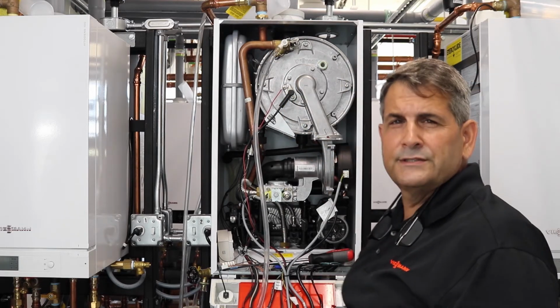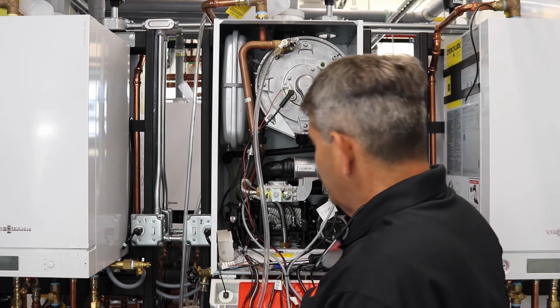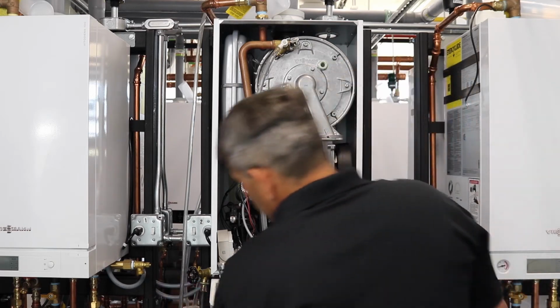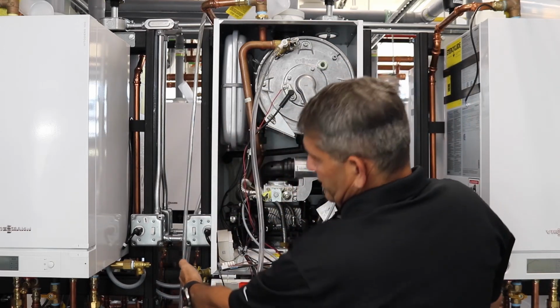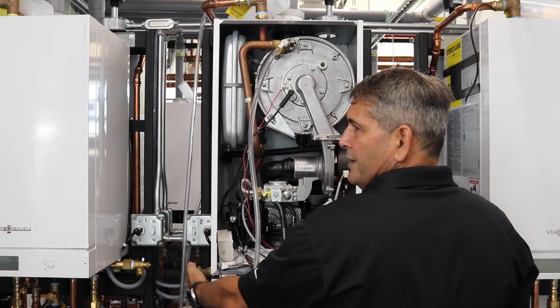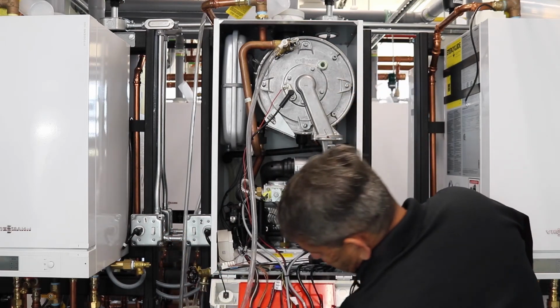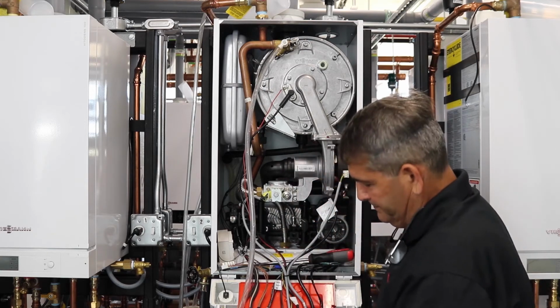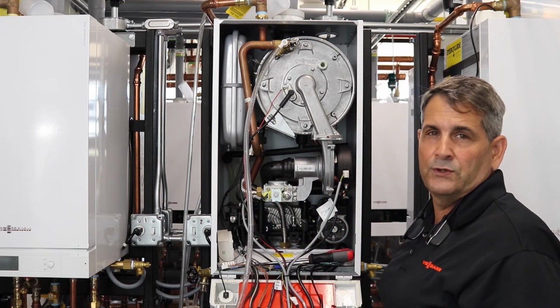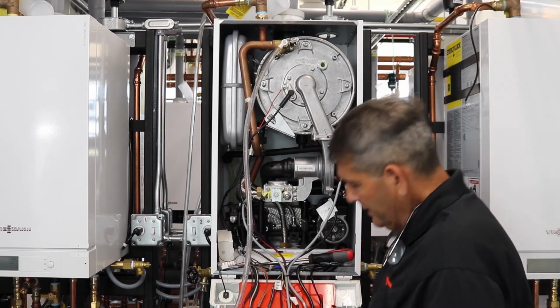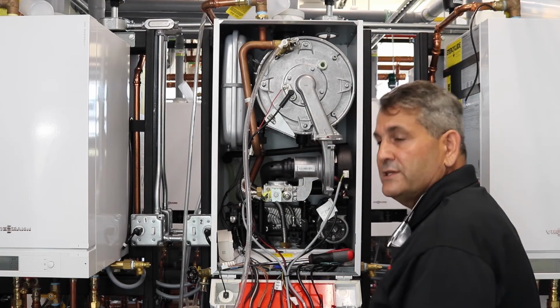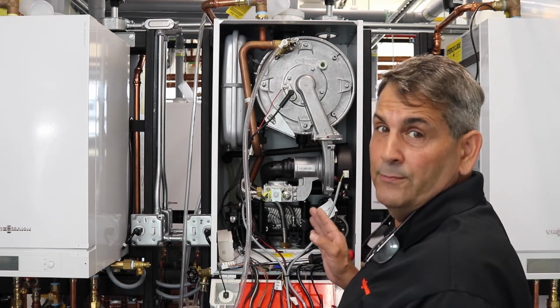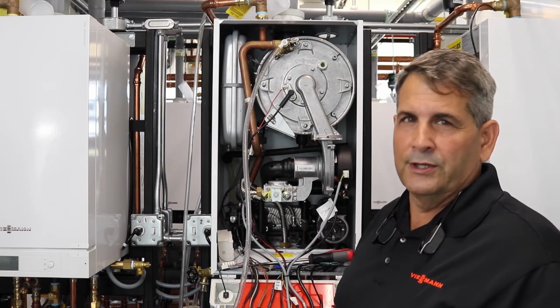We'll fire the boiler to see if we have any more air in there. If we do, then we're going to purge it out through our isolation. Here on the left-hand side, there's a boiler drain that we install. And then on our boilers here, we always put our shutoffs on the supply and return so we can isolate the boilers. And then you can just shut the one on the left-hand side off and make sure you're feeding water into the boiler, and then purge the boiler completely.